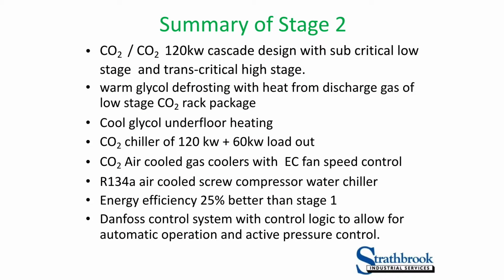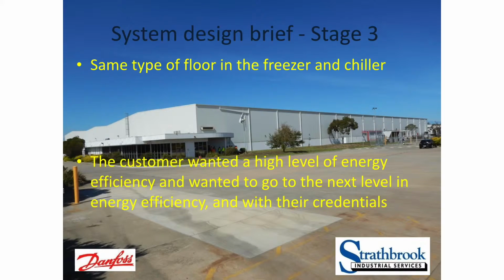So we had a transcritical high stage, a subcritical low stage, and a water chiller to make sure the thing never ran supercritical. We had the same glycol defrost system, but this time heated from a less expensive source, but we still had a R134A screw chiller to economise the whole thing. So the final project we finished at the end of last year. This one's in Melbourne.